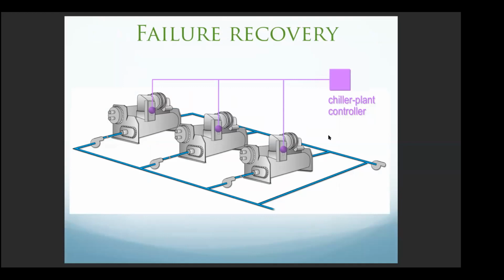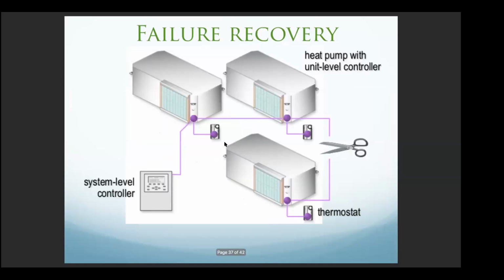Failure recovery. So if there's a chiller plant in a scenario where this chiller is the primary and it fails for some reason, or the cord gets cut, the chiller plant controller is smart enough to know that it may not be responding and the chiller has failed, and it will switch over to the next chiller to be used as the primary chiller to make sure that the building gets what it needs in terms of supply water temperature. Similar example with failure recovery.